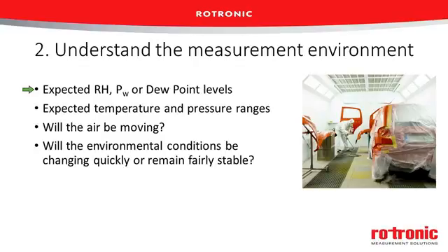The other thing about the environmental conditions is, will the environment be changing quickly? And if it is changing quickly, will you need to know about that change, and how quickly will you need to know as it changes? That can go to the performance of the instrument and how quick the response is. So those are some questions about understanding the environment.